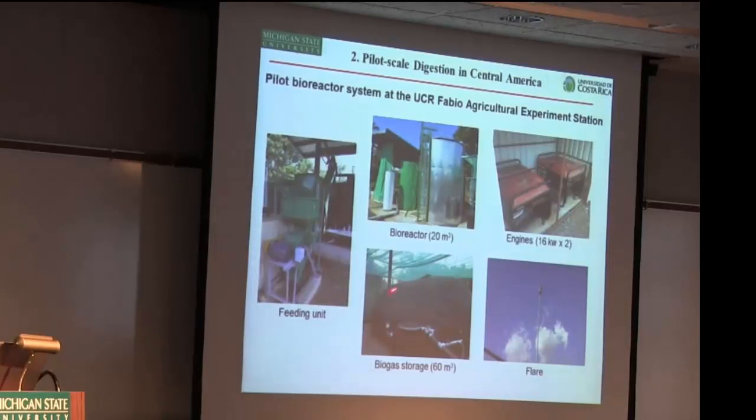There are a lot of anaerobic digesters in Central America and Latin America, but they're more of this bag style, where the digested material is in the same bag where you're storing gas. In those cases, the bag is never really insulated, so you have a lot of temperature fluctuations throughout the day. Even though Costa Rica is a relatively warm climate, nighttime temperatures dip quite a bit, so you would easily see inside a bag digester a 10 to 25 degree temperature change over the course of 24 hours. That's a pretty big fluctuation for this microbial community. In these systems that aren't temperature controlled and work in ambient conditions, we don't see really good conversion, and we don't see clean, high quality, high volumes of biogas.